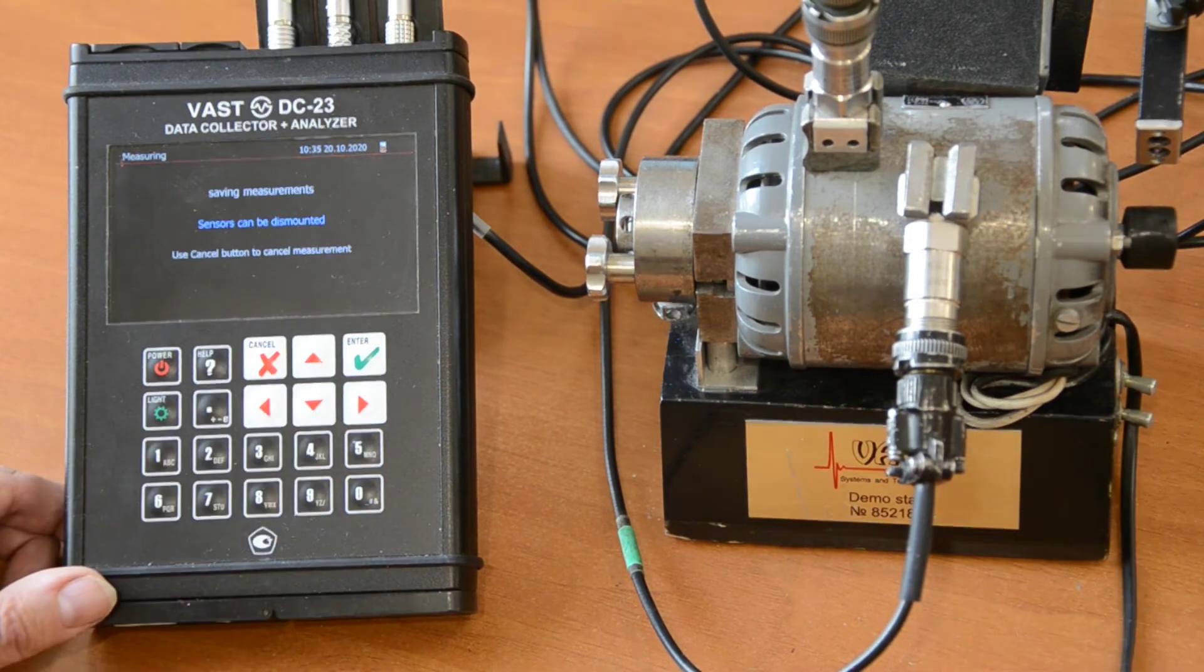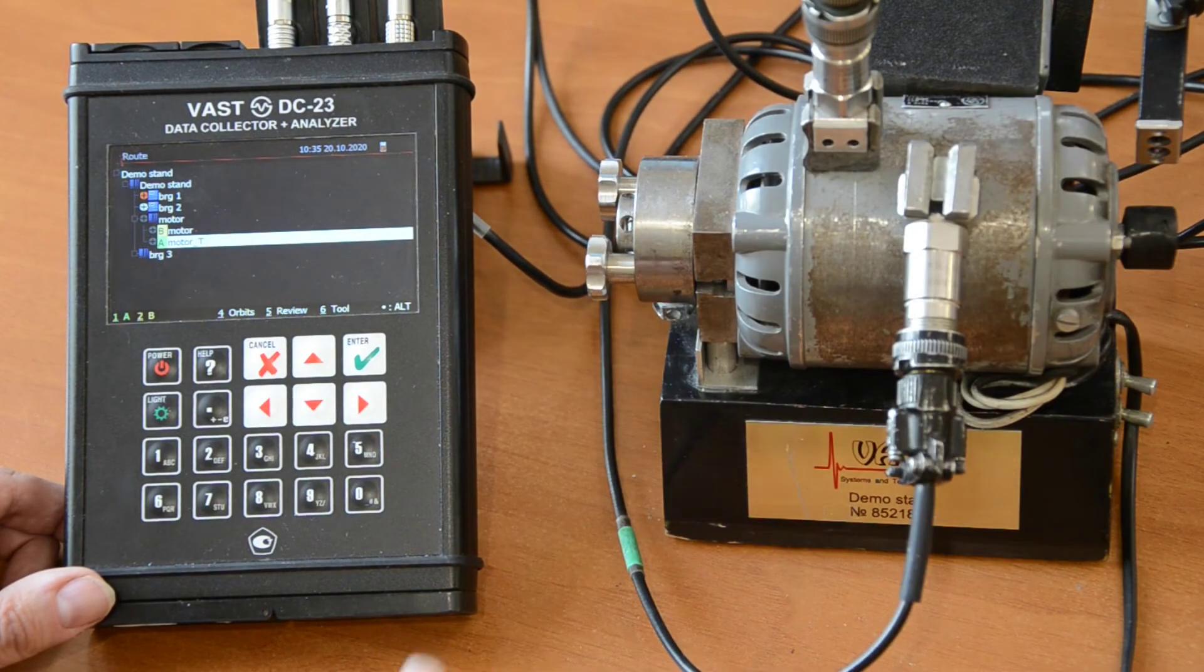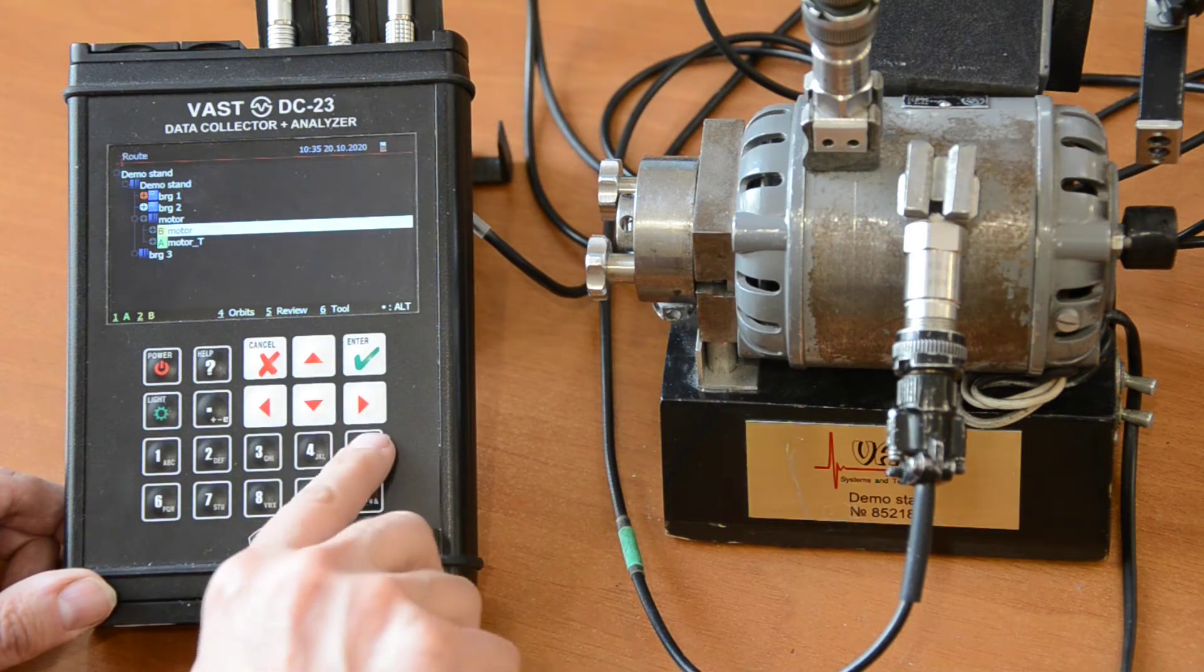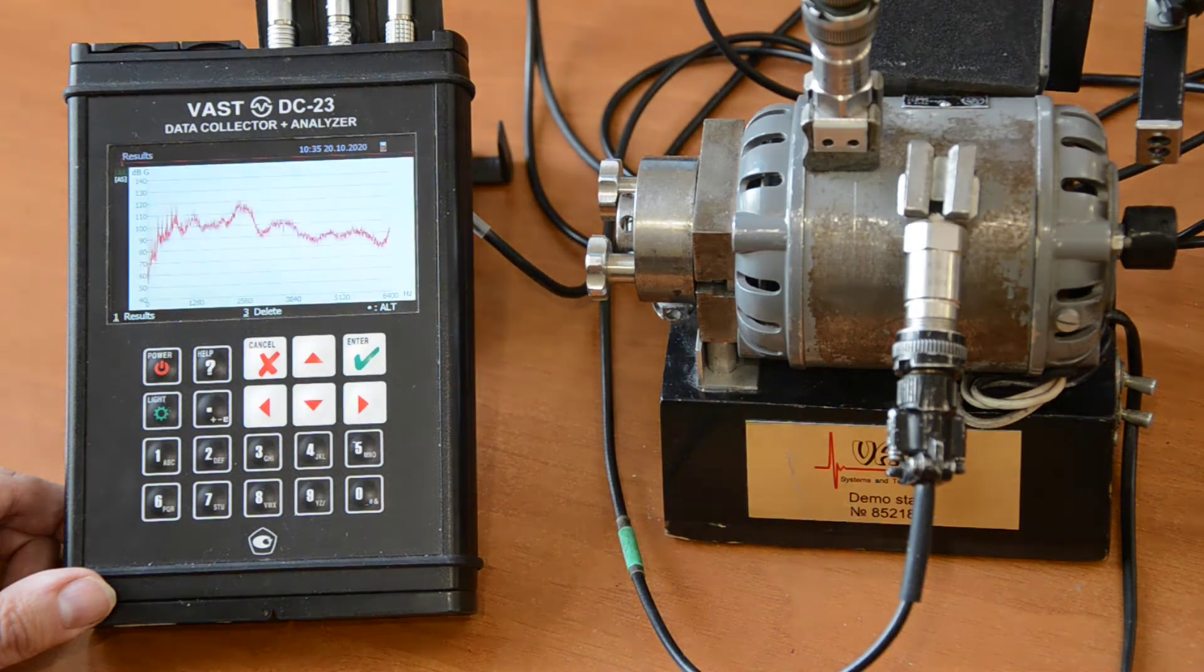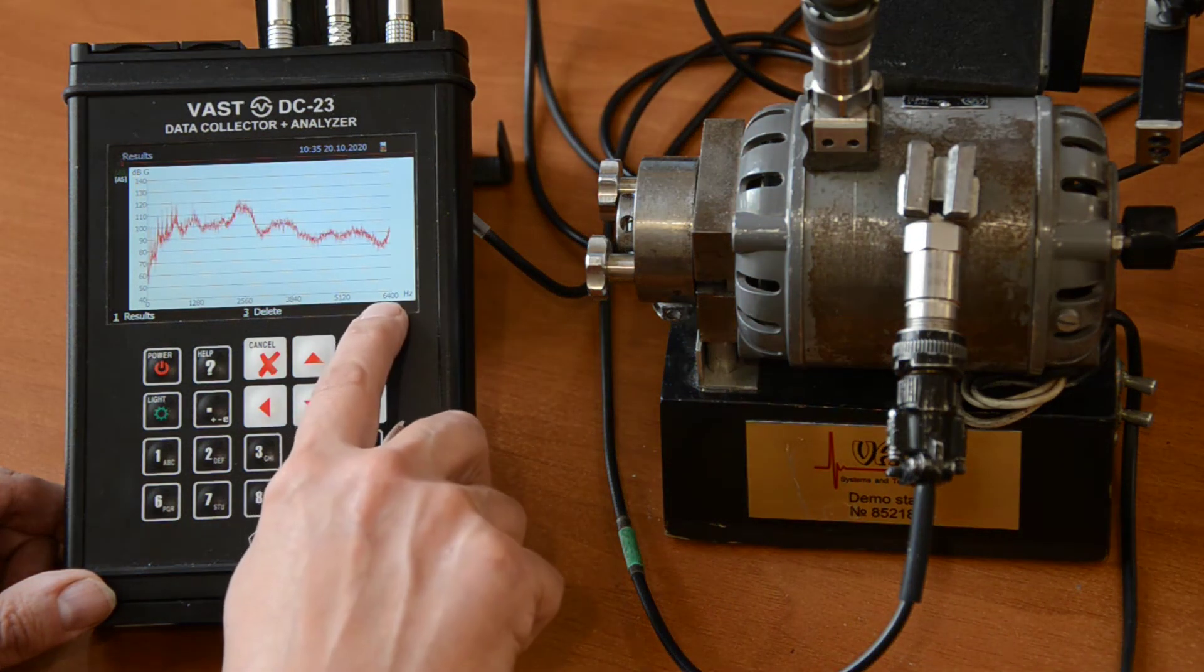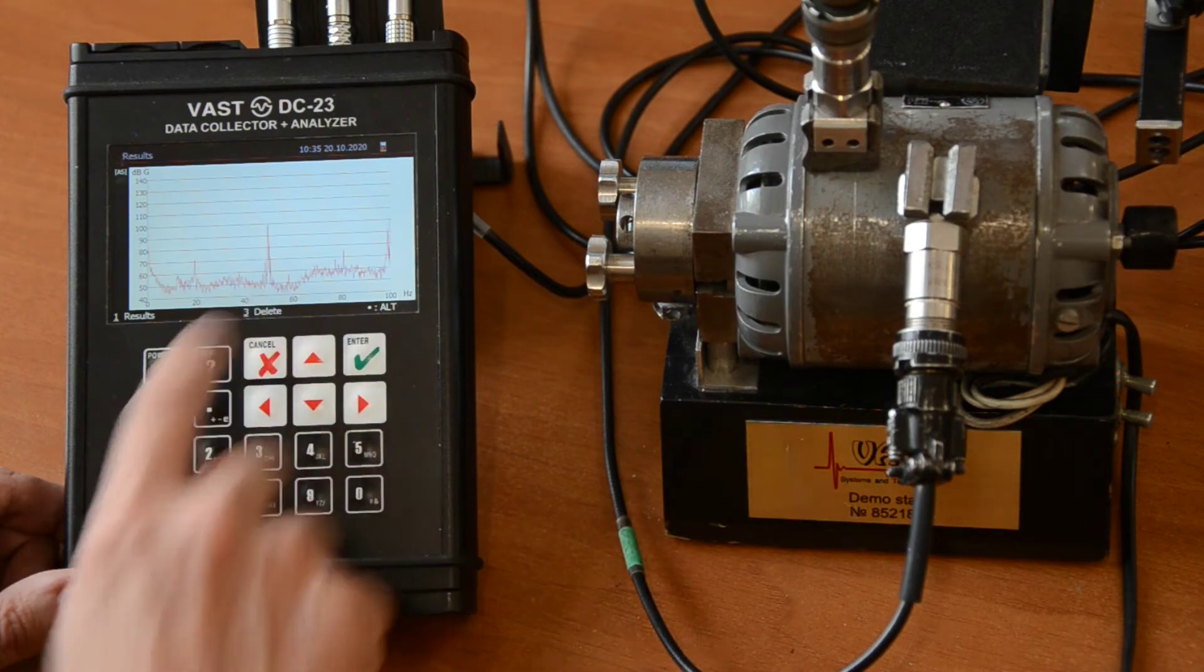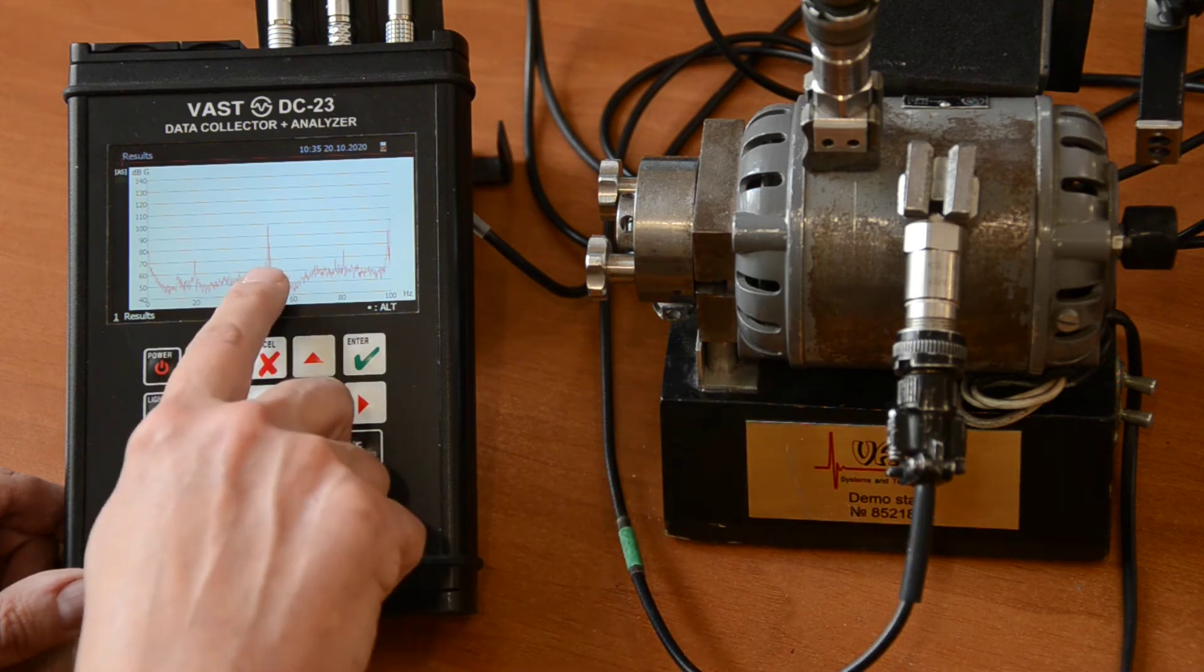The data are collected. Now we have some processing. And you can take the accelerometers and go to somewhere. So, let's see what we have measured. We can review the data. And here we have two spectra. One up to 6400 Hz. And another is very high frequency resolution around the rotation speed. I have 3000 RPM motor, and this is my rotation speed.